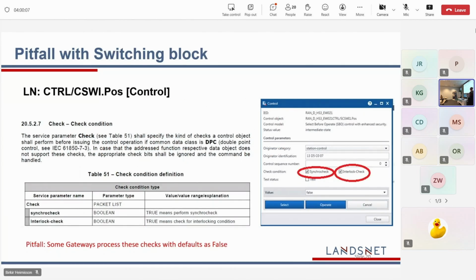So there are these condition settings, so you can choose if you synchro check and interlocks, pretty much bypass them. And there was a glitch in the gateway we had there. It had the settings that it should get these condition settings from the 104 command coming from the control room. But when it didn't include it, it kind of dropped the synchro checker, so it bypassed the synchro check while closing this.